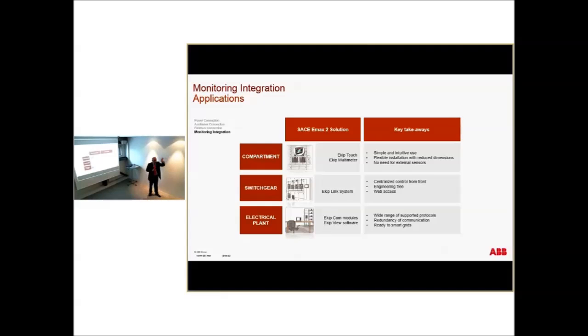So you can insert the information or read the information or interrogate the breaker, both from the release and from the multimeters. On top of that, you have a digital output, 24 volts. So in case you want to supply, because this HMI needs to be supplied externally by 24 volts and 230 volts, you have also the supply that from the HMI goes to the breaker. So you don't need to make two cabling, but just one cabling for one device. And this is a quite flexible solution.